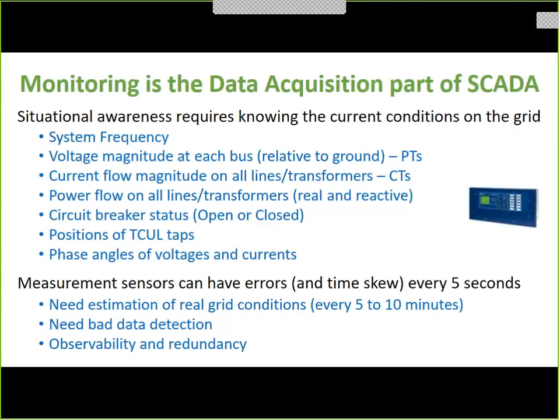We monitor the position of tap-changing under-load transformers, TCULs. And the phase angles is a fairly modern thing to do. Monitor those angles on the voltages and the current. It's not so obvious what we're going to do with that measurement, but it's nice to sit and look at it and say, aha, I know what it is. I know the angle on all the bus voltages, and I know the angles on all the currents. What you do with that is yet to be decided.